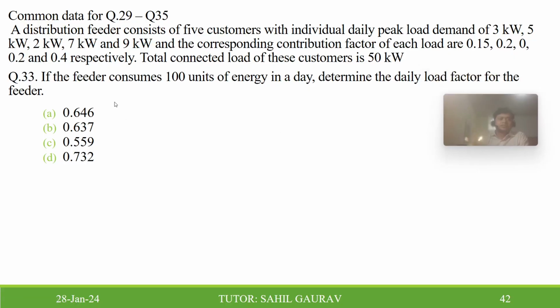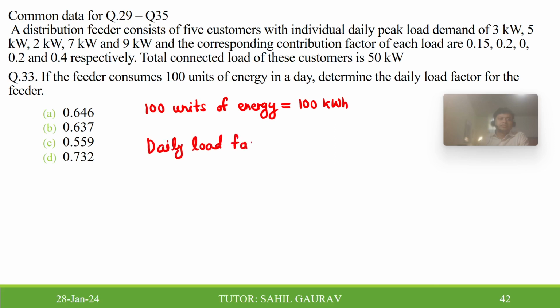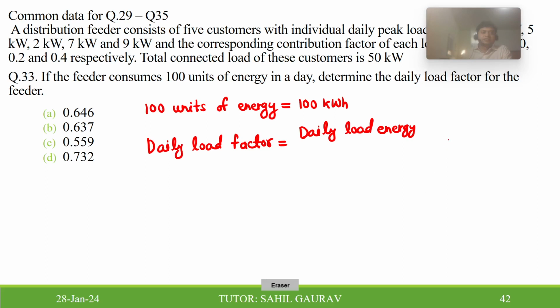If the feeder consumes 100 units of energy in a day, determine the daily load factor for the feeder. So 100 units of energy means 100 kilowatt hour. And daily load factor we can write, that is daily load energy consumed divided by peak demand into 24.